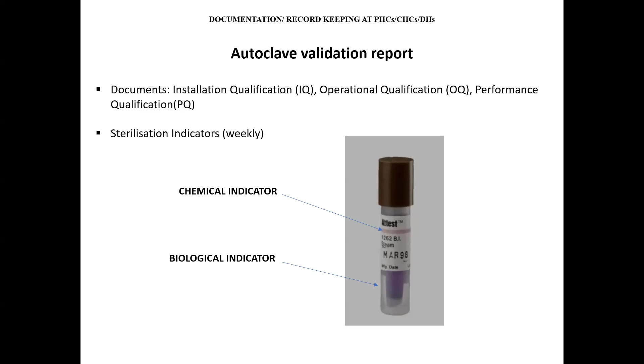So this is the biological indicator. The whole thing is the biological indicator, but the chemical indicator is just this pink strip over this vial. You should use this weekly if possible, but for this you will need an incubator. For those where it is not possible, you can use only the chemical indicator, which is a kind of tape that you can paste on the waste that you will sterilize. And where incubators are available, you can use the biological indicator, this particular vial.